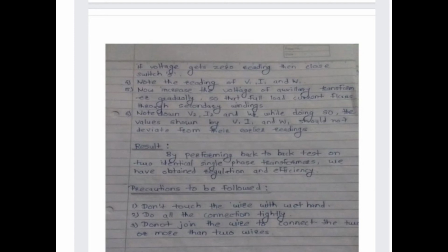Now increase the voltage of the auxiliary transformer gradually so that full load current flows. Sixth is to note down V2, I2 and W2. While doing so, the values shown by V1, I1 and W1 should not deviate from their earlier readings. So the result is that by performing the back-to-back test on two identical single-phase transformers, we have obtained regulation and efficiency. So this is the result of this practical.